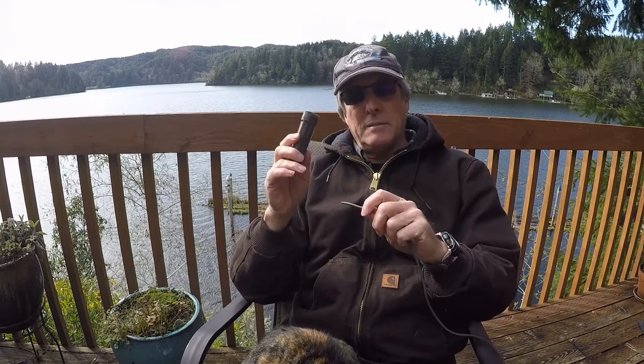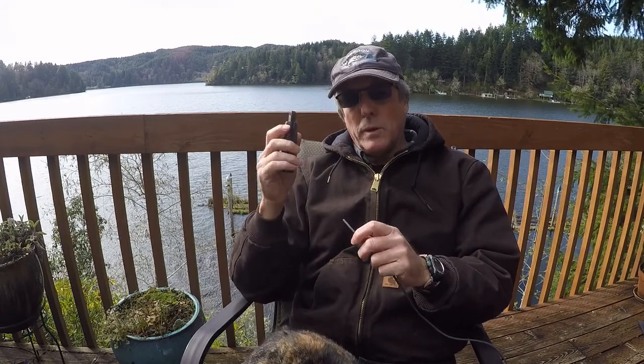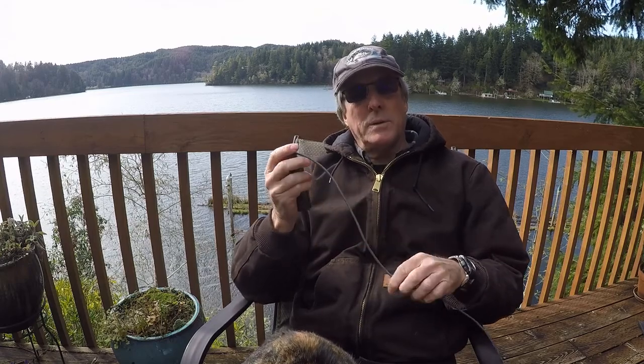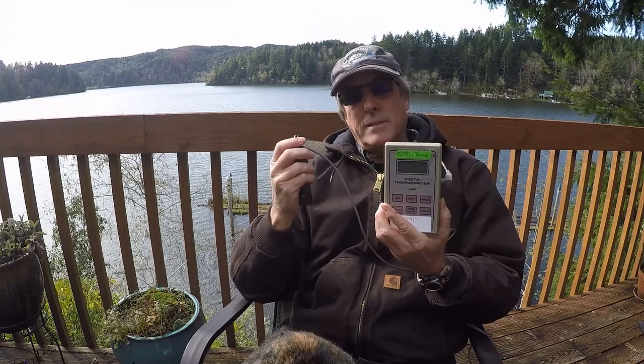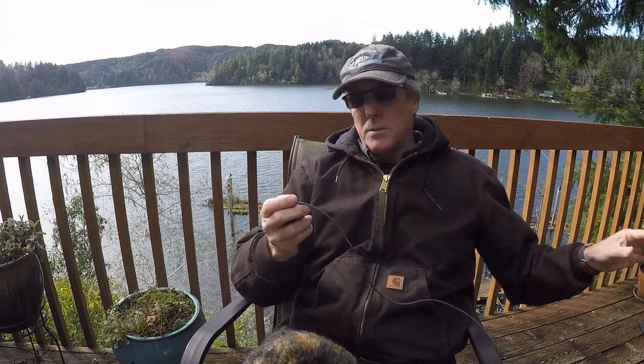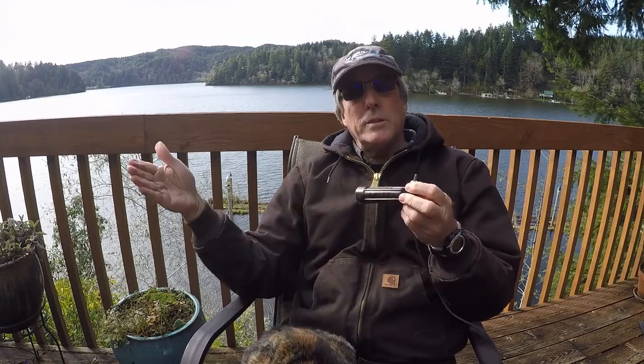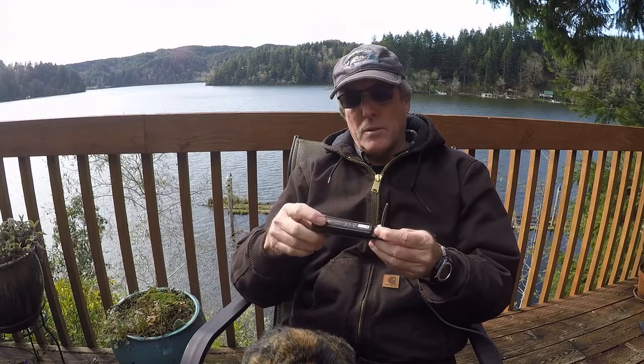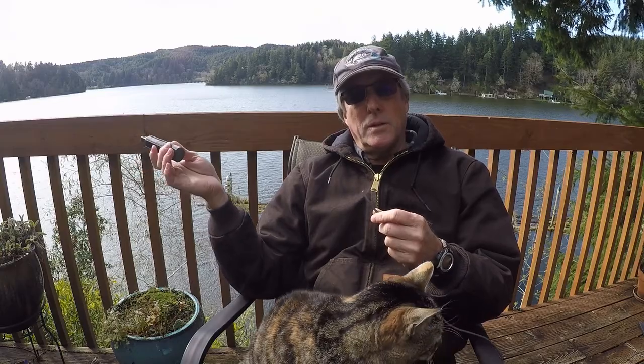So what we'll do is, first thing is go to our computer and set up this to read once every minute for its recording, and then we will start it on exactly the 0 point, so that we'll synchronize our phone or our watch with the time in here, so that we will know when it's taking the temperature, and then we will take a manual temperature with the NIST thermometer at the same time. By doing that, we'll be able to look, and we'll do that about 5 times over 5 minutes or so, and then we'll do it in the ice bath, and then we'll do it in the warm water bath.